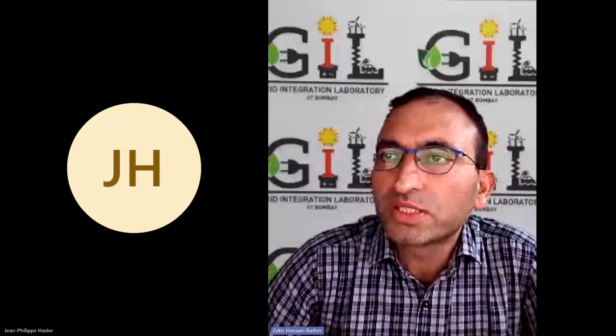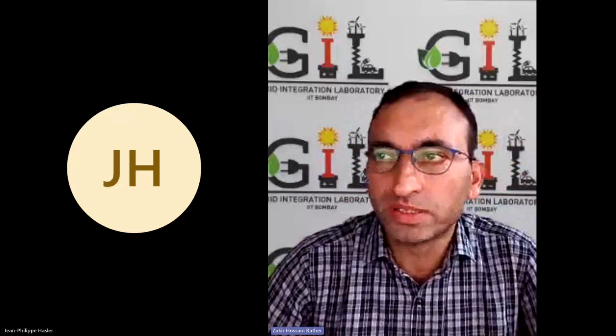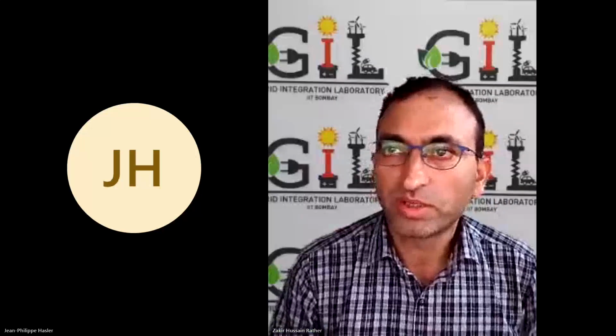Next is, does any standard, IEEE or IEC, exist to test if the inverter is grid following or grid forming? If yes, are major players and industries following any of these tests for their converters before delivery? John, again, I think you would be the right person to reply to this question, about whether there is any practice of testing in the industry for this grid forming technology.